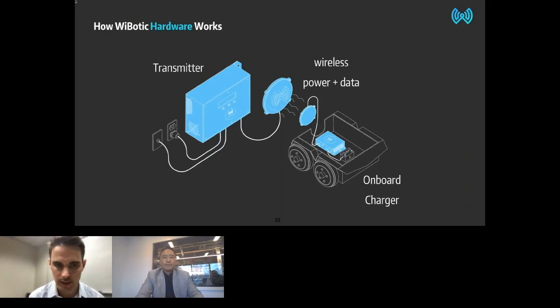But when you select lead acid, we generally have the third stage of float charging. It can be time sequenced, the current and voltage limit for different TPPL versus gel versus AGM, right? There are slight differences in the voltages required for that third float stage, or some even require a pulsed stage. One of the nice things about the way we architected our system is a lot of that is, for us, firmware.